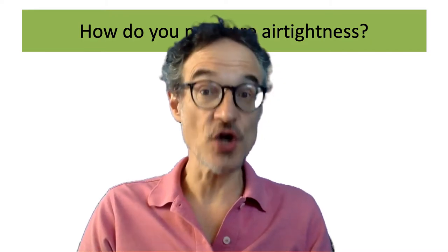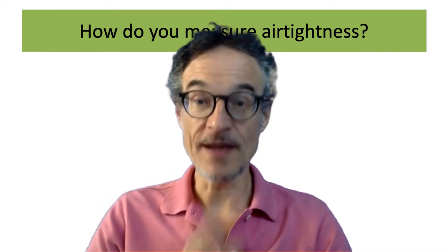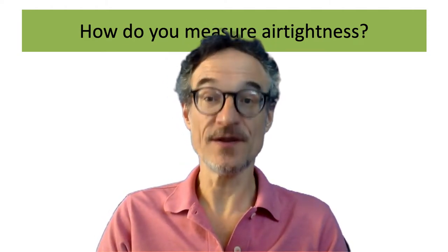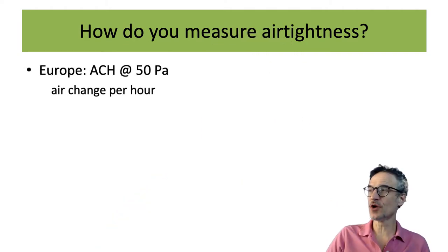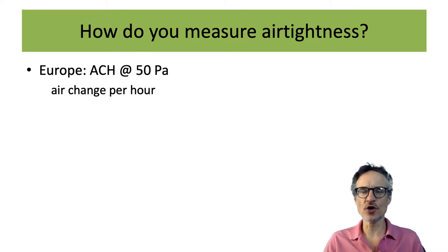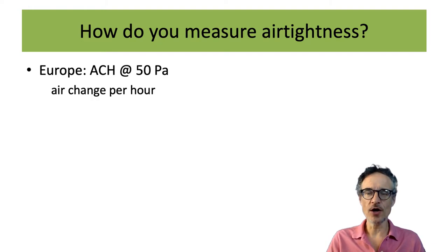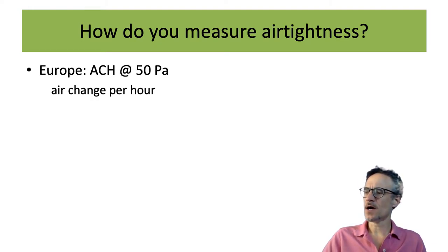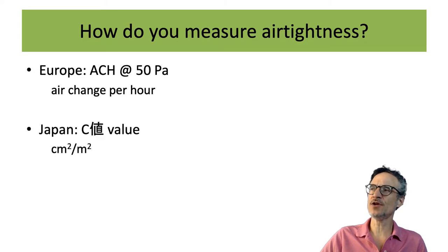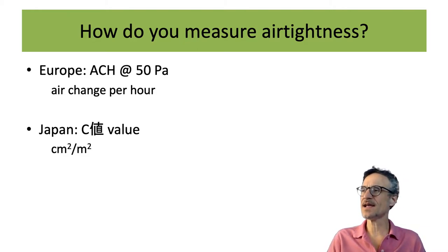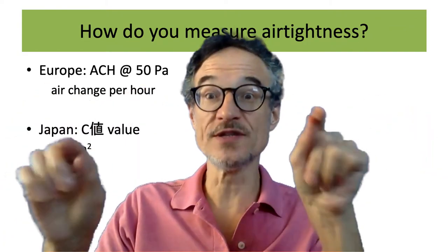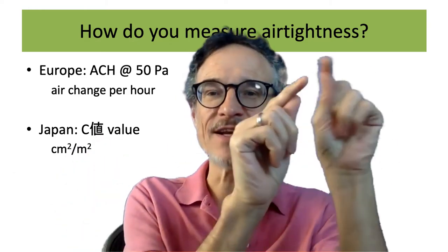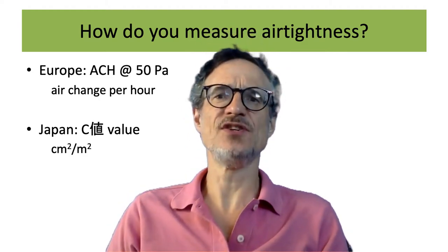We can measure most things if we try, and if we want to make a low energy building we need to measure — so we can find out how much energy we're actually using. In Europe, the measurement is usually air changes per hour at 50 pascals. Japan uses the C-value (shichi), which is in square centimetres per square metre — if you imagine any wall has lots of holes and you add up the area of those holes, that gives you the C-value.